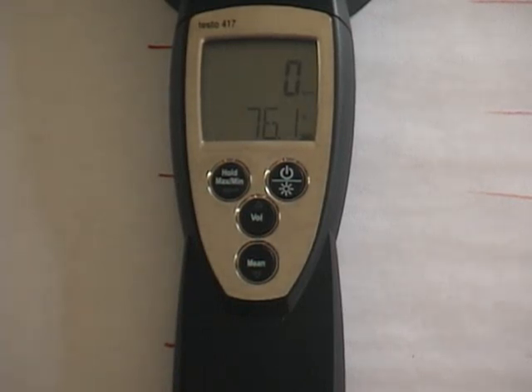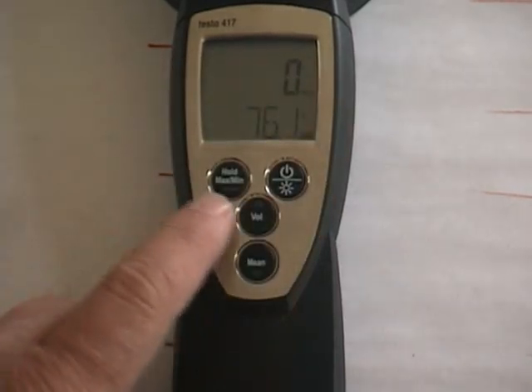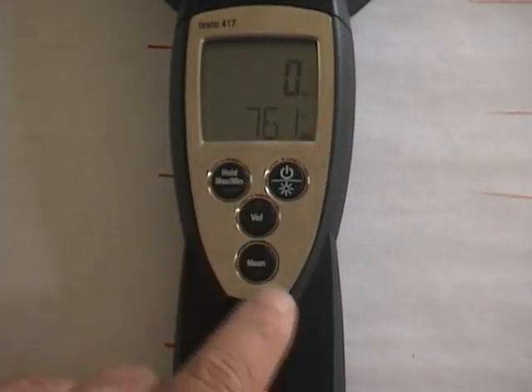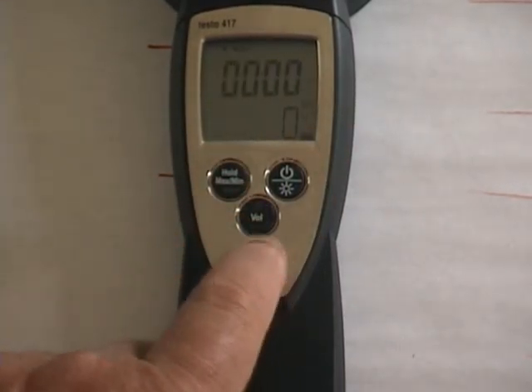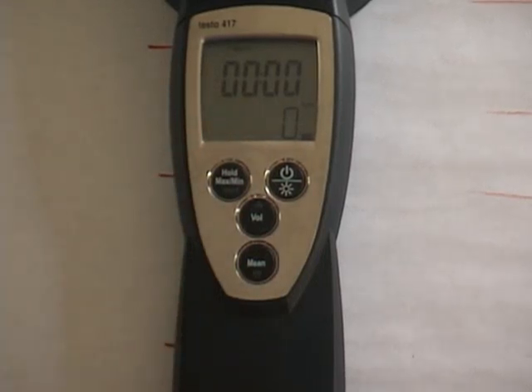You press the mean button twice until you get four digits across the top. So here's the mean button, bottom one. Press it twice. I've got four digits across the top. You'll see a little clock face and mean typed out there, and that means you're in the right screen to take a timed traverse where it averages your readings across the entire grill face.